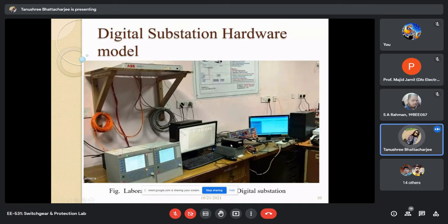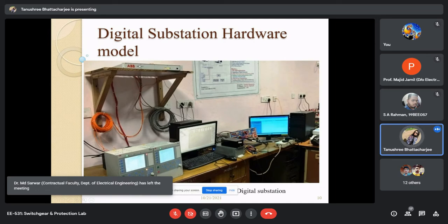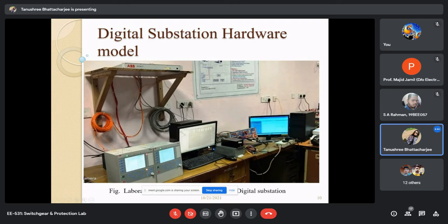Now what is a merging unit? This is a unit which is used to convert the signal from analog to digital, because IEDs are intelligent electronic devices and they can understand only digital form of communication. That is why we need to first transfer the V and I into sampling form, then it becomes a digital signal and it will be transferred to the IEDs. Now all of these are connected through LAN wires, but the IEDs will be connected through these patch cables, so that communication will be faster.